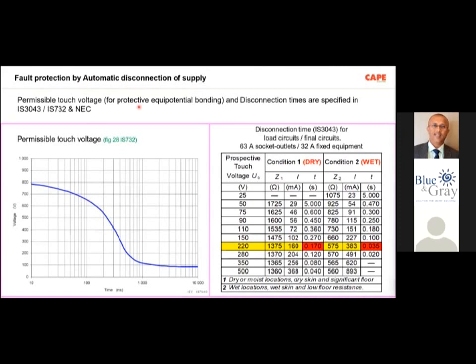But if you go to the definition, automatic disconnection of supply is a protective measure which is achieved by protective equipotential bonding and automatic disconnection of supply. That means this safety measure consists of 2 things. One is protective equipotential bonding. On this particular graph, what you are seeing is the permissible touch voltage. The maximum fault voltage inside your installation must be reduced to less than this particular voltage.